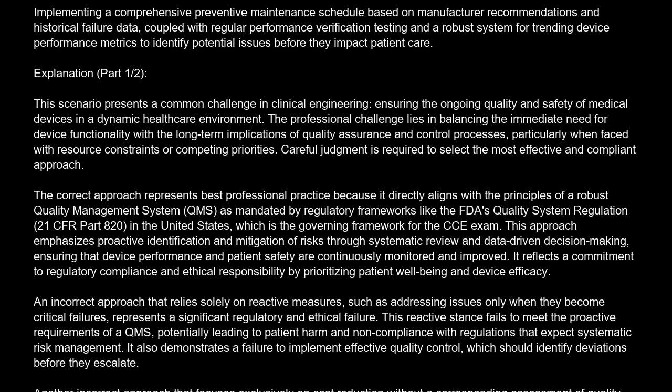Implementing a comprehensive preventive maintenance schedule based on manufacturer recommendations and historical failure data, coupled with regular performance verification testing, and a robust system for trending device performance metrics to identify potential issues before they impact patient care. Explanation: this scenario presents a common challenge in clinical engineering, ensuring the ongoing quality and safety of medical devices in a dynamic healthcare environment. The professional challenge lies in balancing the immediate need for device functionality with the long-term implications of quality assurance and control processes, particularly when faced with resource constraints or competing priorities.